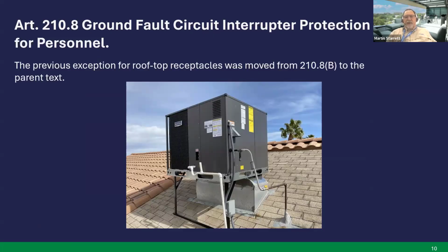I don't know if you've heard or not, but May is National Electrical Safety Month. And one of the safety items we have in the electrical industry is the ground fault circuit interrupter. So it's kind of good that we're in our Chapter 2 today for that reason. One of the things in the parent text is the previous exception for rooftop receptacles was moved from 210.8(B) to the parent text. That was originally over the other dwellings, so now it'll apply for dwellings as well. If you remember what that says, that is that ground fault circuit interrupter protection has to be readily accessible, but that exception for rooftop receptacles says it only has to be accessible from the roof. Next slide, please.